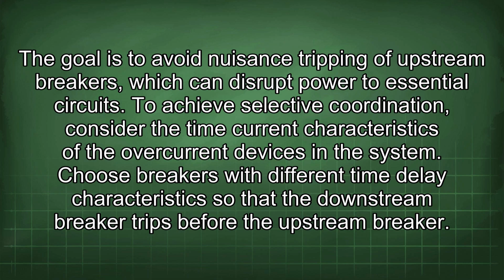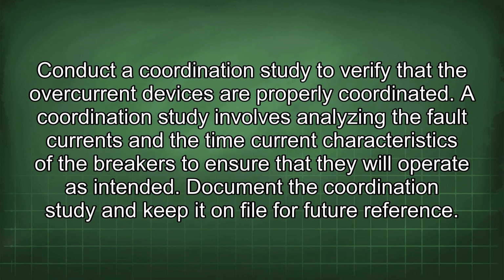To achieve selective coordination, consider the time current characteristics of the overcurrent devices in the system. Choose breakers with different time delay characteristics so that the downstream breaker trips before the upstream breaker. Conduct a coordination study to verify that the overcurrent devices are properly coordinated. A coordination study involves analyzing the fault currents and the time current characteristics of the breakers to ensure that they will operate as intended. Document the coordination study and keep it on file for future reference.